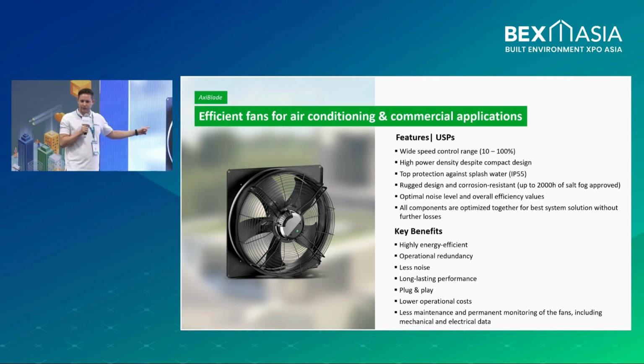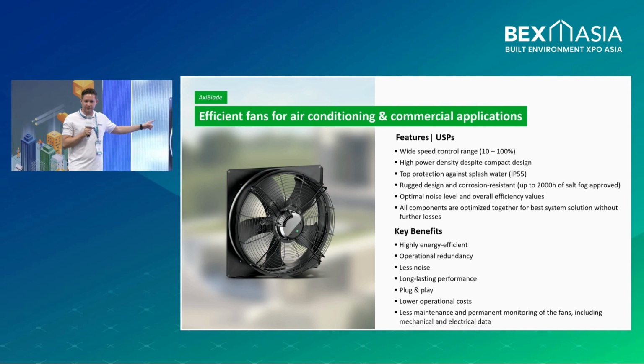We talked about cooling towers before. Cooling towers have very harsh corrosion, and fans and motors usually need to be exchanged very often. We have fans tested up to 2000 hours of salt fog testing, and also tested with cooling tower water, and they survive, giving high reliability. This is very important because such high corrosion, especially in a tropical climate like here in Singapore, can happen, and our fans are a perfect solution for that.